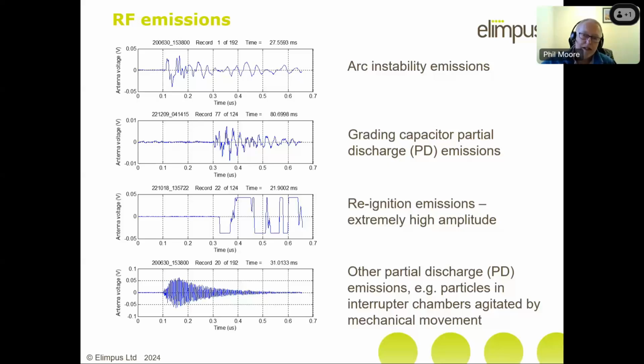But if you were to see a big difference between one phase and the other two, that tells you something has gone wrong. So if there's a lack of emissions, it usually means the arc is not where you expect it to be. And if there's a large number of emissions, it could be that there's been some damage done inside the interrupter.